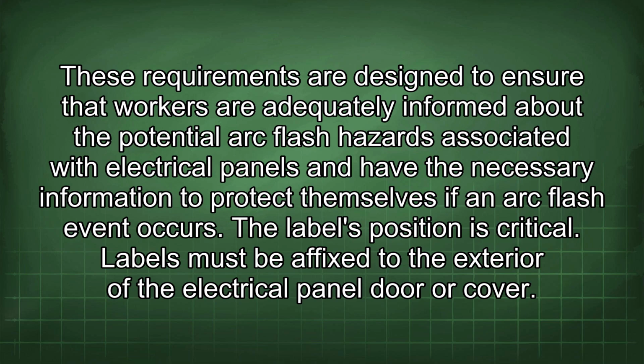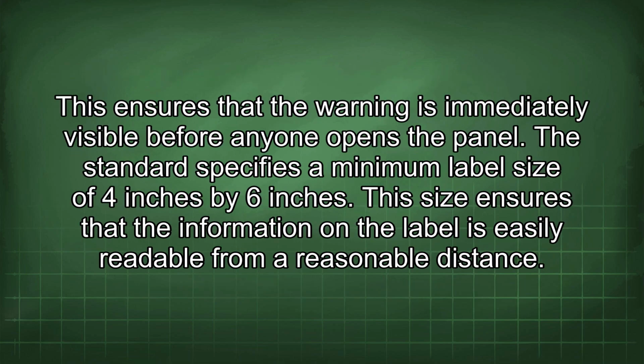The label's position is critical. Labels must be affixed to the exterior of the electrical panel door or cover. This ensures that the warning is immediately visible before anyone opens the panel. The standard specifies a minimum label size of 4 inches by 6 inches. This size ensures that the information on the label is easily readable from a reasonable distance.